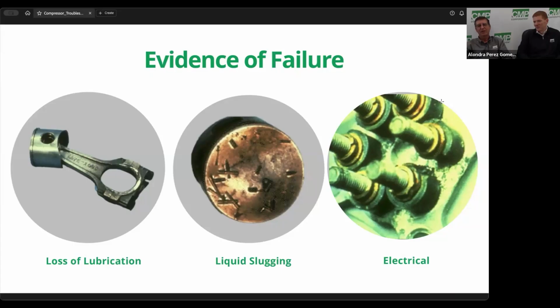Because even in the remanufacturing business, we had a compressor on the roof of a facility, and it was vibrating, shaking so bad that I said, well, it's got to be a broken rod. It couldn't be the valve plate. So after we took the whole compressor down off the roof and put the new compressor in, I got back to the shop and I could have changed the valve plate in 30 minutes. It was just a valve plate, and it was shaking so bad. So like I said, the whole purpose of this is so that you don't make the same mistakes that we made when we were doing service work. Yeah, I know. And I agree. I've done lots of that.